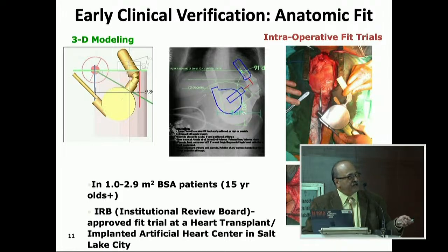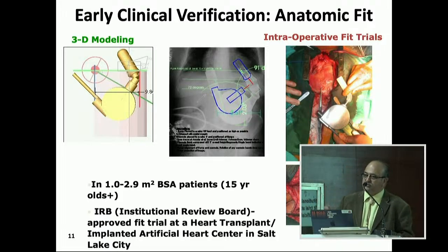So we had a sterilized model of a pump, non-working, just sitting, and had approval from the hospital. So anyone who came for a heart transplant or a LVAD could sign up to be evaluated first with this model, so we could see whether it worked or not, the angles and the implantation technique. All that stuff is so critical for the implanting team.